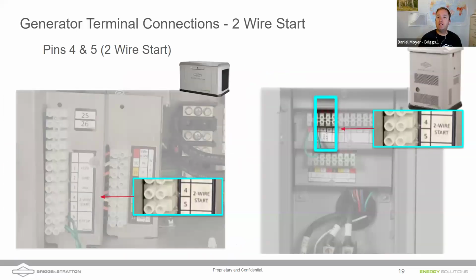So now what we've done is we're taking a look at a picture of inside of our generator wiring bay. Out of pins 7 and 8 on the Solarc, you're going to land your two-wire signal to start on pins 4 and 5 inside of the generator. On the left is one of our horizontal units, that's our 18, 20, 22, and 26K generators. And on the right is our vertical 13K generator. So this is what it's going to look like when you jump in there and look at where you want to land inside the generator as well.